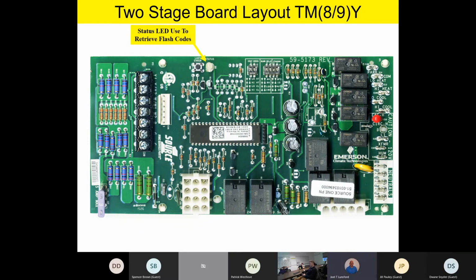Okay. When you say the last 5 errors, when you press the last error button, does it immediately show you the most recent error, or does it show you all 5 of the last errors in a row? That's an excellent question. It'll show you the most recent one, and then if you depress it again, it'll show you the next one, and so on. The most recent will always be at the very top of the stack, so to speak. And then you can continue going through those error codes by depressing that button. If you hold the button down for 5 to 10 seconds, it'll clear that memory. Good question. Any other good questions or comments? Okay, good. Excellent.